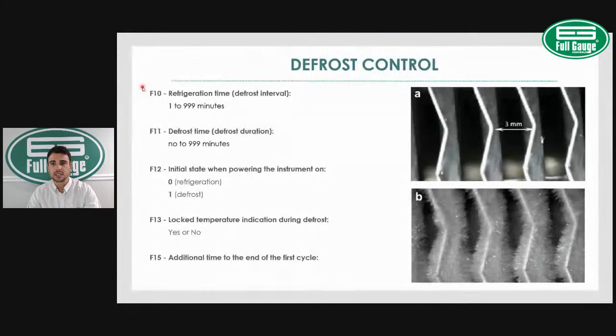Another relevant defrost parameter is F11. F11 is the defrost duration. You can set this to 0, which will disable the defrost function, or you can set it all the way up to 999 minutes. The average defrost duration, what I mostly see on a medium temp refrigeration unit, goes from 20 to 40 minutes. That's the normal range I mostly see out there in the field.